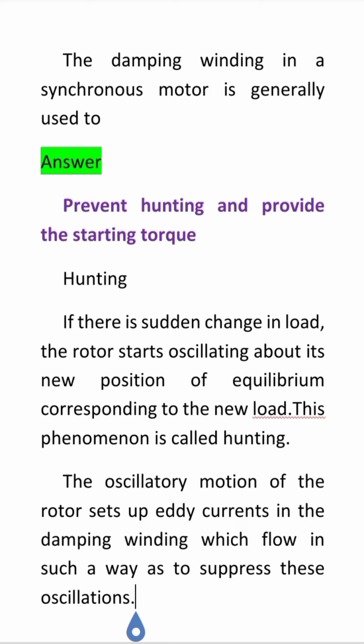Hunting means if there is sudden change in load, the rotor starts oscillating about its new position of equilibrium corresponding to the new load. This oscillatory motion is called hunting. How is it prevented by the damping winding? The oscillatory motion of the rotor sets up eddy currents in the damping winding which flow in such a way as to suppress these oscillations. In this way, the damping winding prevents hunting.